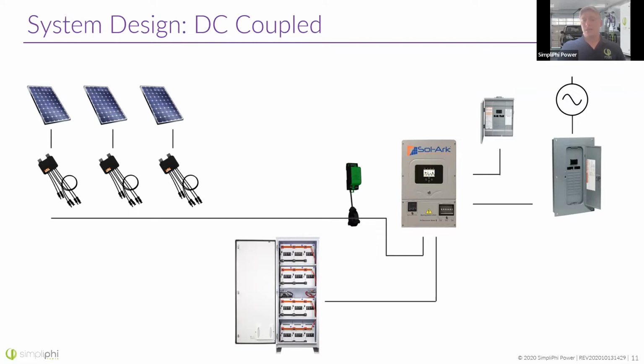Another design here, just to highlight that sometimes the DC bus bar is hidden within the inverter already. So you may have a DC connection for your batteries and your PV array at separate locations within the inverter, and you might not see it visibly, but they are on that same DC bus somewhere internally.